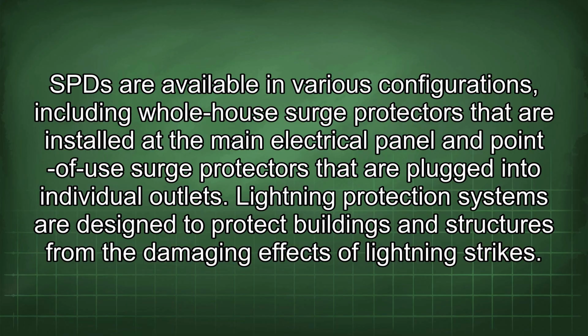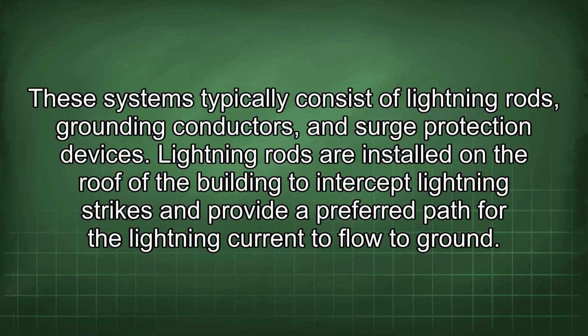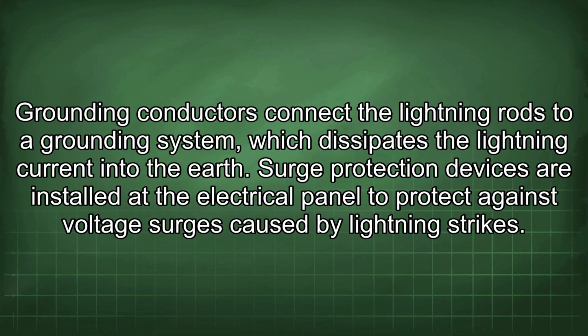Lightning protection systems are designed to protect buildings and structures from the damaging effects of lightning strikes. These systems typically consist of lightning rods, grounding conductors, and surge protection devices. Lightning rods are installed on the roof of the building to intercept lightning strikes and provide a preferred path for the lightning current to flow to ground. Grounding conductors connect the lightning rods to a grounding system, which dissipates the lightning current into the earth. Surge protection devices are installed at the electrical panel to protect against voltage surges caused by lightning strikes.